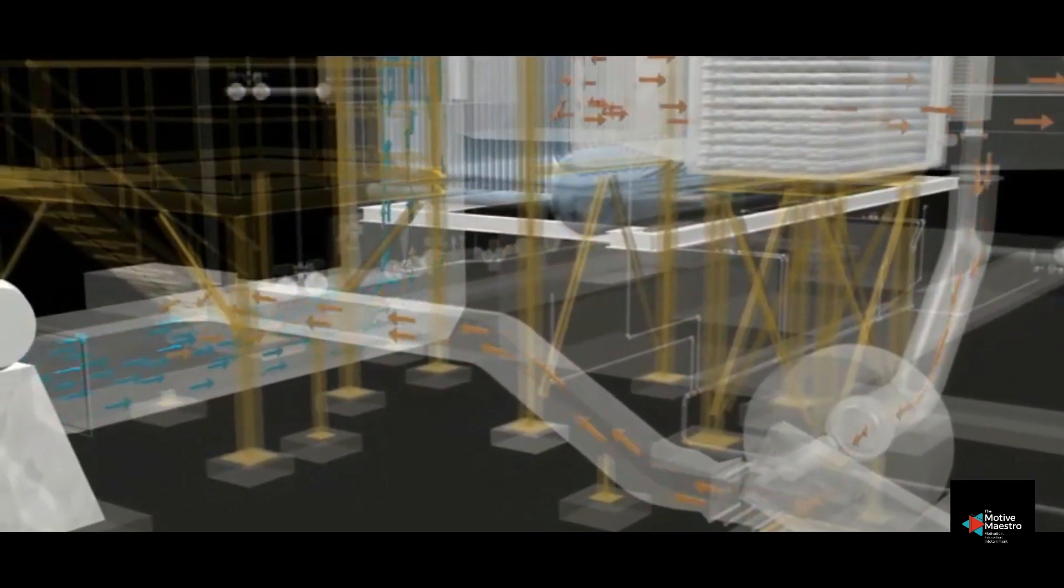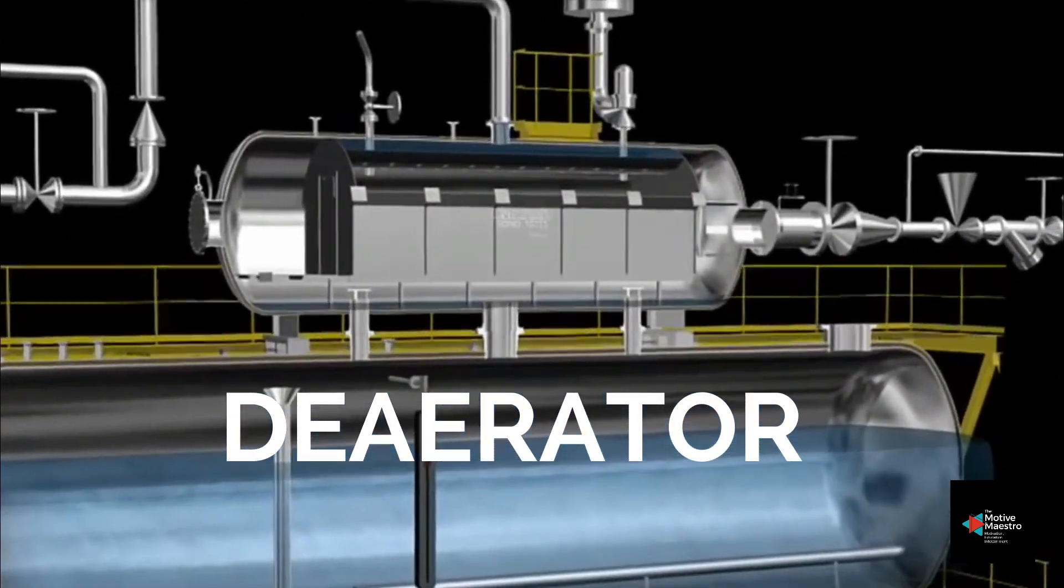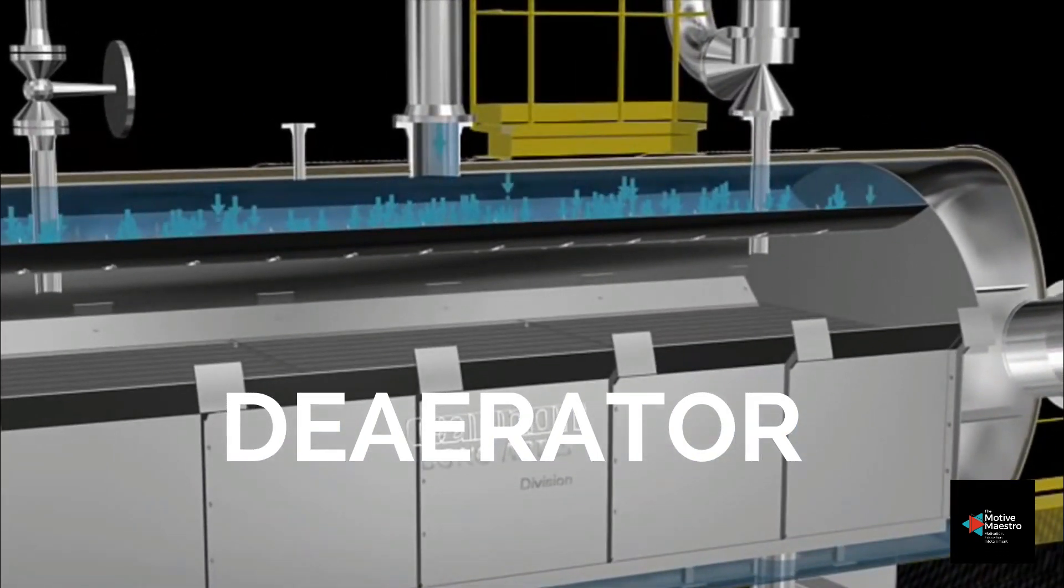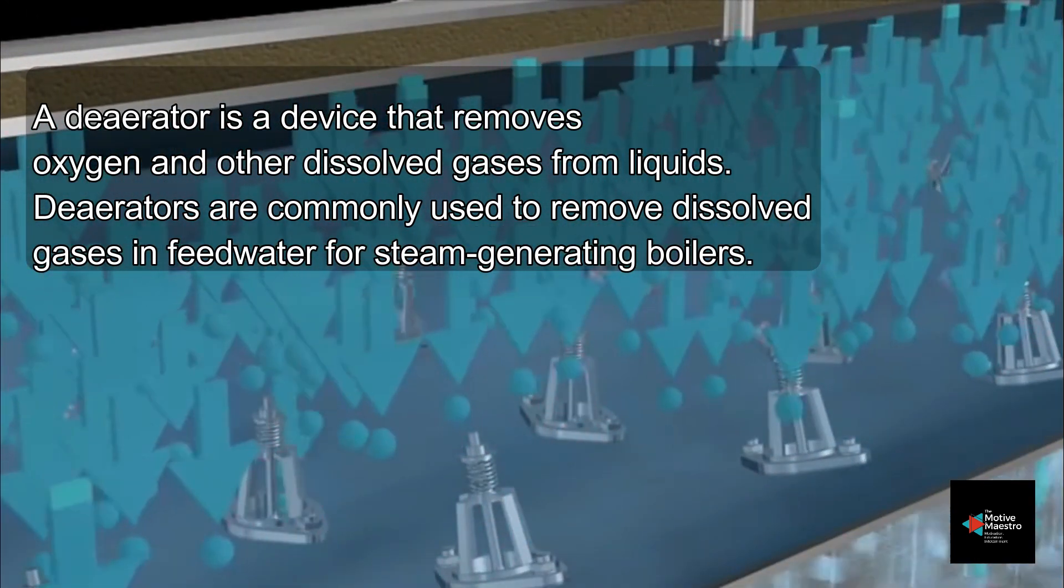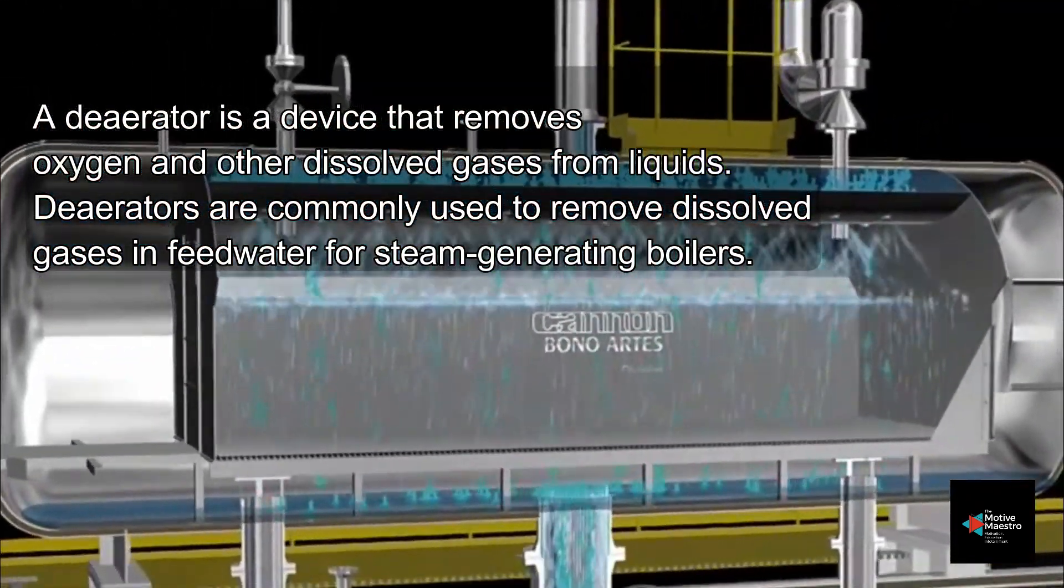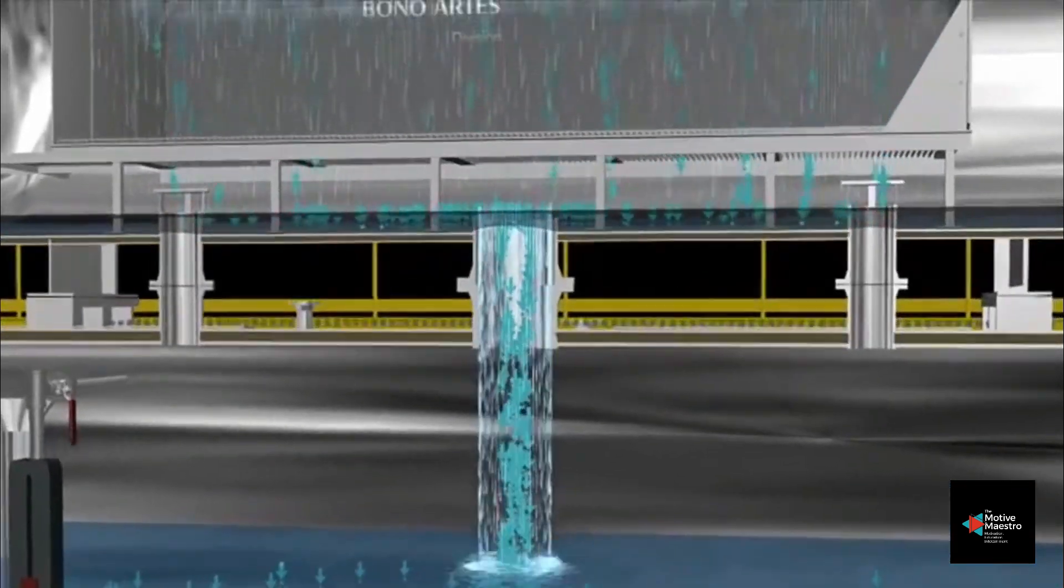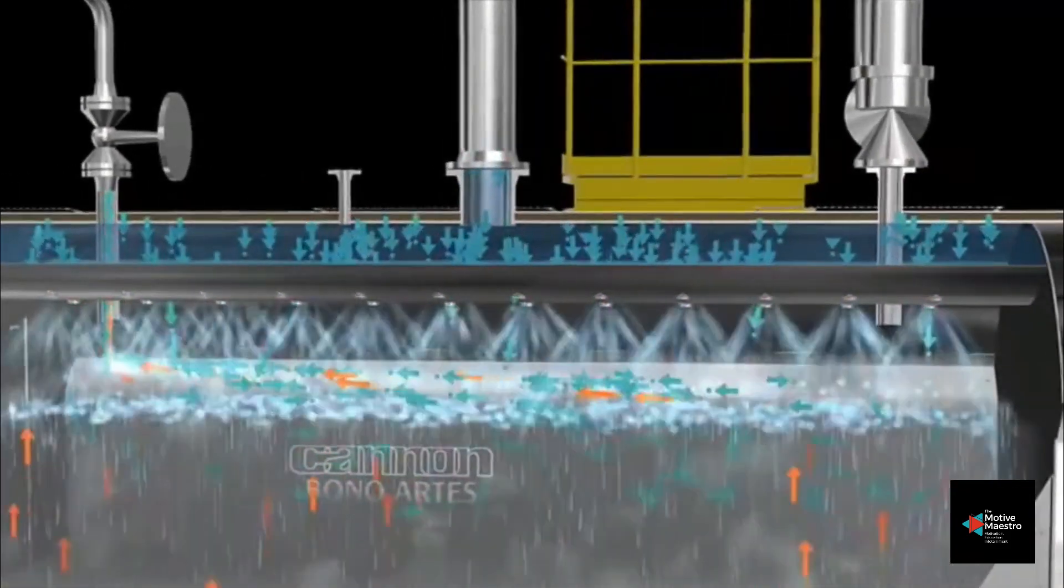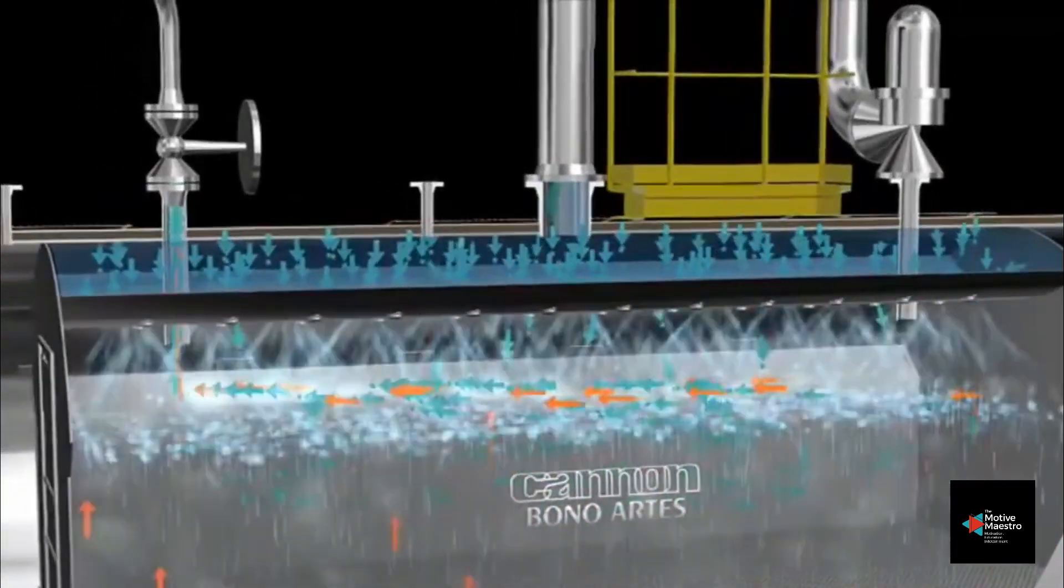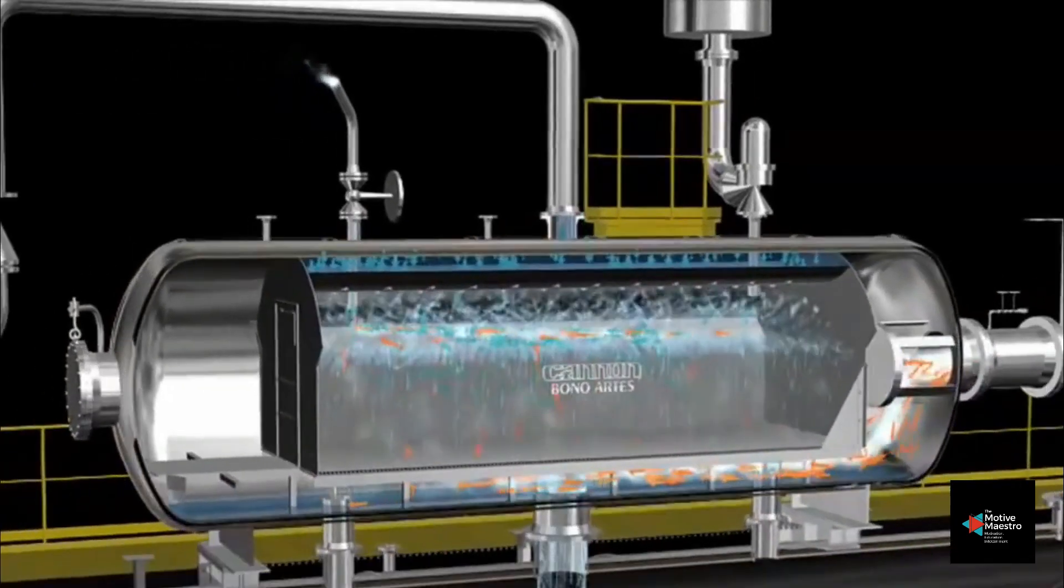So let's have a look at our water circuit now because it's the water that gets fed to the boiler in order to generate steam. We've got a makeup water inlet. Makeup water feeds to a deaerator. When we talk about makeup water we are essentially talking about the water that's added to the system and then treated before it becomes boiler feed water. You can't just take water from a city grid or from a lake or a river and put it into a water tube boiler. That's not going to work. You will have a lot of corrosion and a lot of problems. So this makeup water has to be treated chemically and mechanically and we do that quite often in a deaerator. The deaerator is going to reduce the oxygen content and the carbon dioxide content of the water. Before the water gets to the deaerator it's going to be filtered to take out those particles that might be floating around in the water.